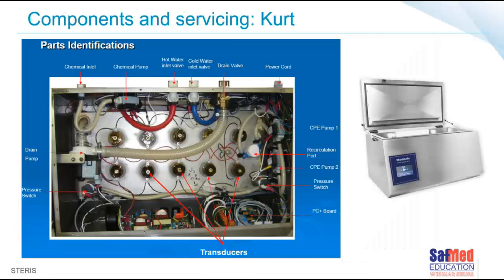So we spoke about the importance that they saw in the published paper; they said it's really important to service the ultrasonic. Is it such a complex device? Does it need servicing? Yes. So you mentioned earlier about the dots, the transducers, as we can see in the photo. They are the chemical inlet ports. There's the chemical pump, the hot and cold water inlet valves. There's a drain valve. There's certain CPE pumps, the recirculation ports, and your PC board. These are all electronic and some movable parts, and it needs to be serviced regularly as per the manufacturer's instructions for use of the ultrasonic cleaner.